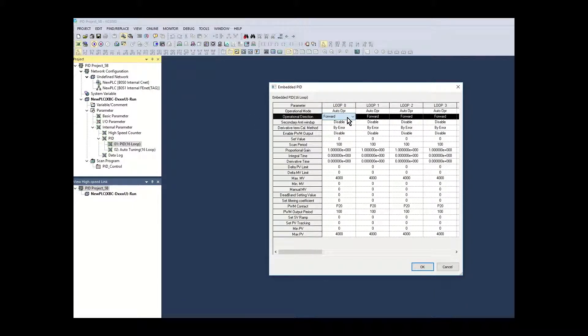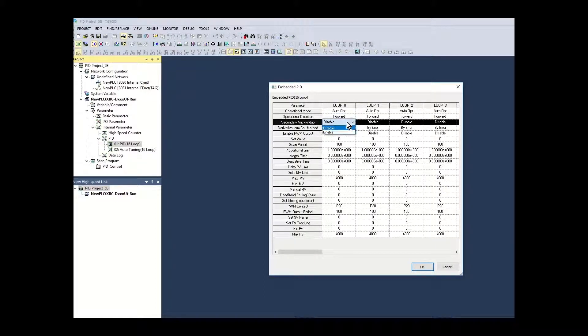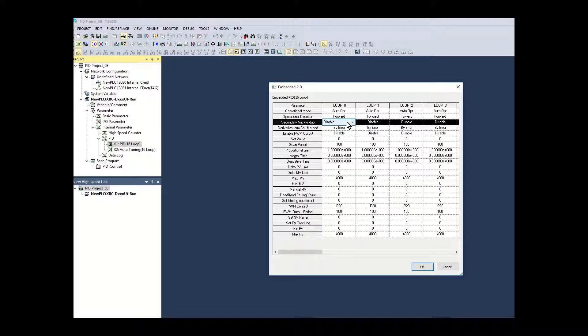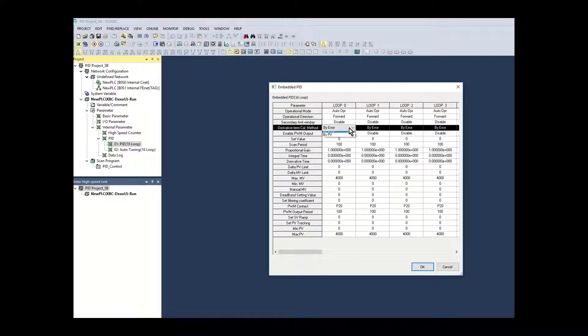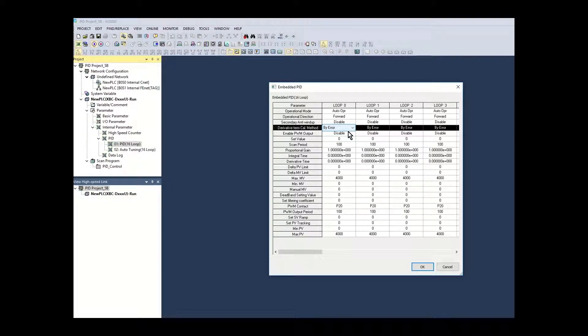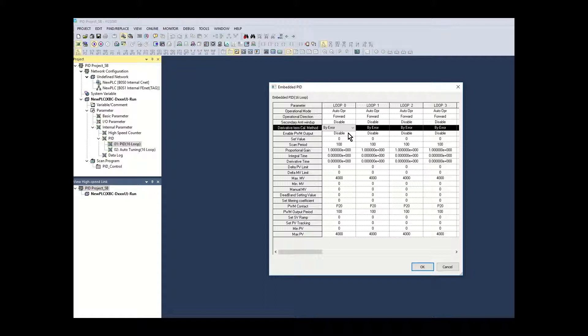Set operational loop direction to forward. Secondary anti-windup disabled. This setting selection enables integral windup prevention. Derivative term calc mode is set for error. This is used when the derivative term is used in the PID calculation.